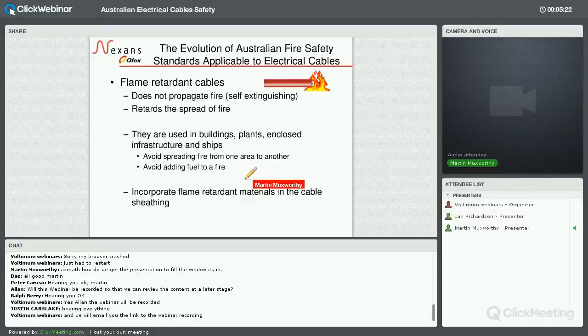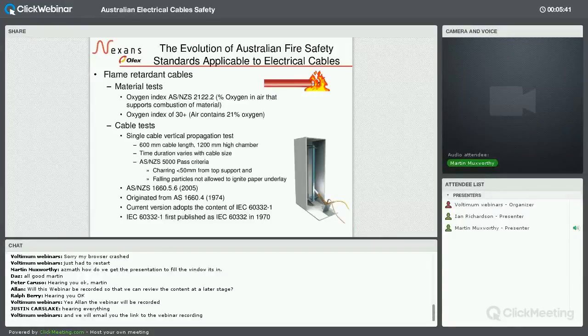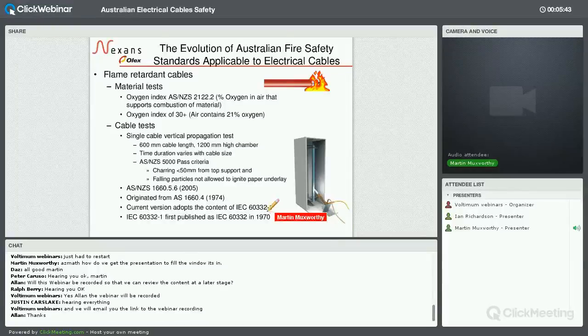I guess the other aspect is that not only do they stop fire spreading from one area to another, they also avoid adding fuel to a fire, so it stops the fire growing in that regard. And what we do to try and make a cable flame retardant is we need to incorporate flame retardant materials typically in the cable sheath, and it's a tricky combination of where you put these flame retardant materials.